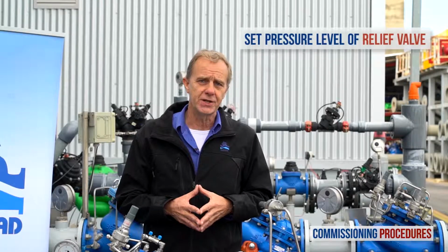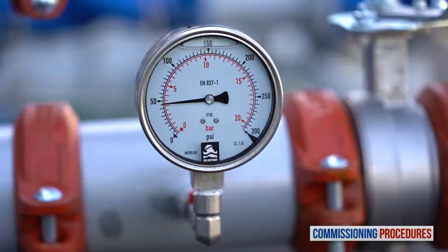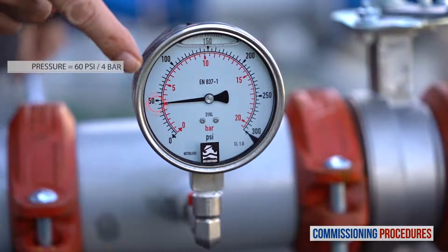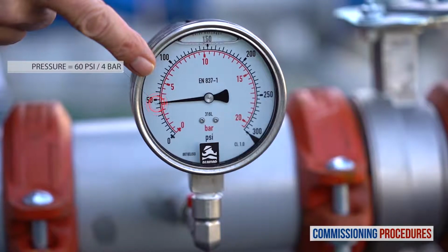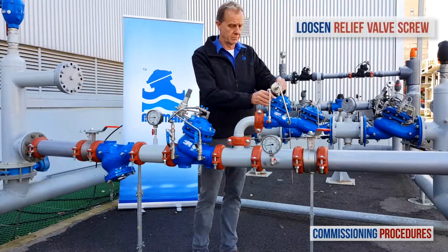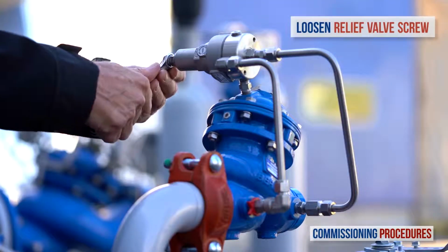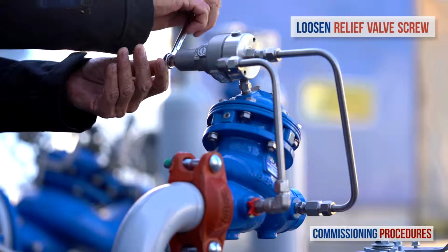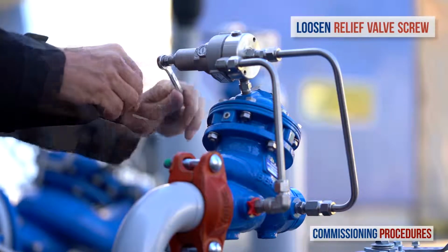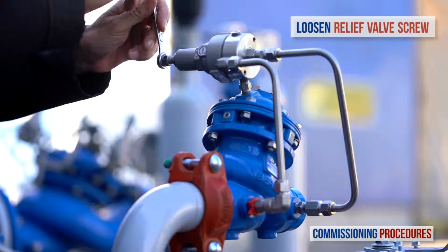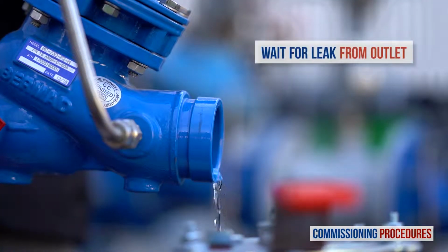The final stage in the commissioning process is setting the pressure level of the relief valve. First off, make sure that the inlet pressure is at the required system level. Now start to slowly unscrew, counterclockwise, the relief valve's pilot screw until the valve opens slightly. When this happens, you should notice a small leak from the valve outlet.